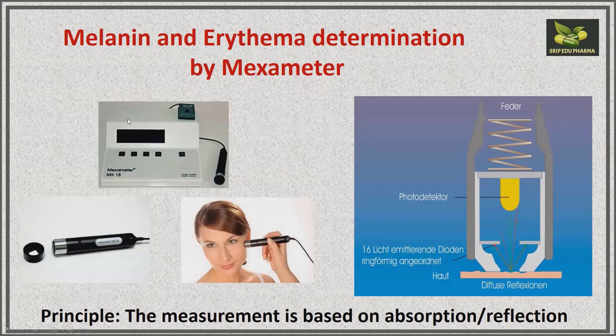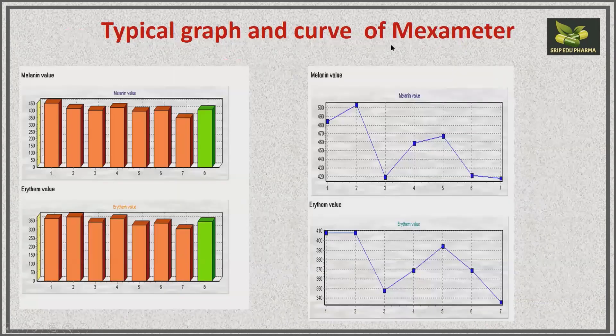For melanin and erythema determination, this is the mexameter MX18 instrument and its probe. In the diagram, there is a photodetector and light is emitted at different wavelengths to obtain melanin and erythema levels. In a single application, you can get values for both melanin and erythema. The typical graph shows seven readings with the eighth being the average, and a corresponding curve is also obtained.